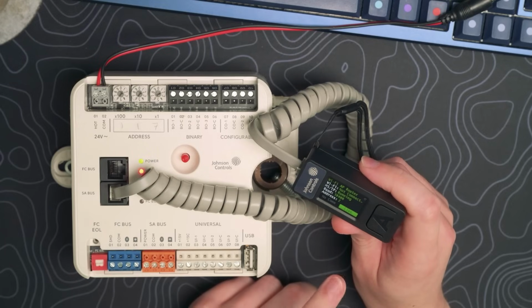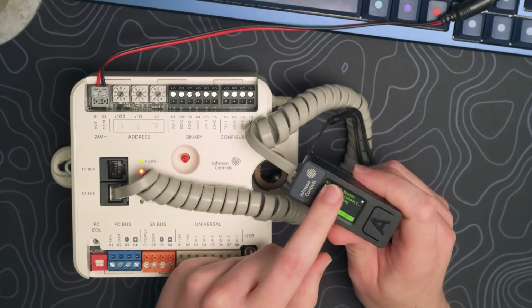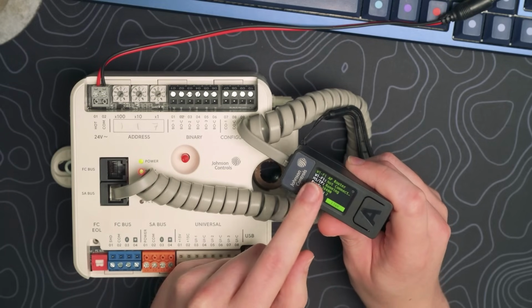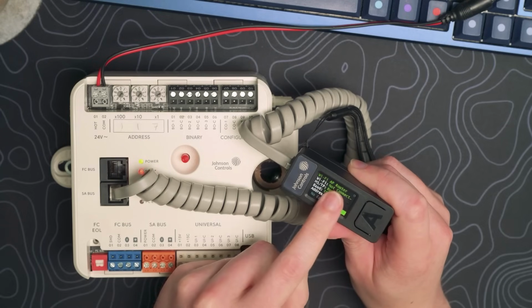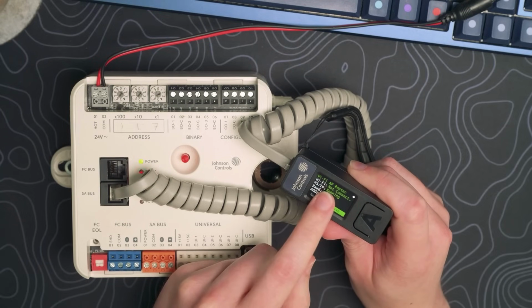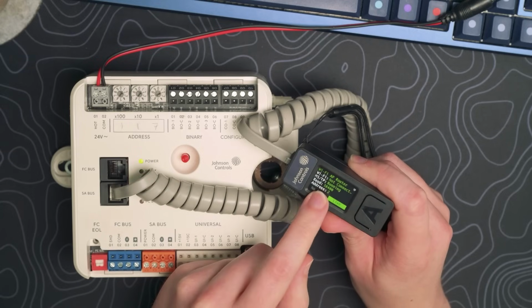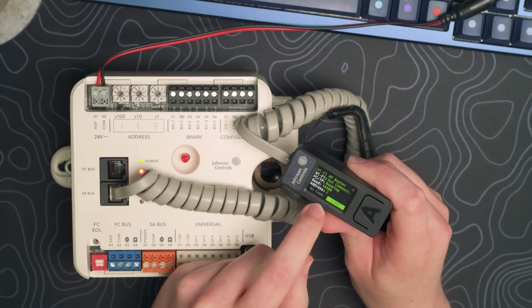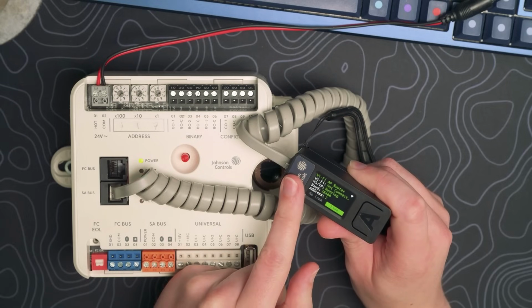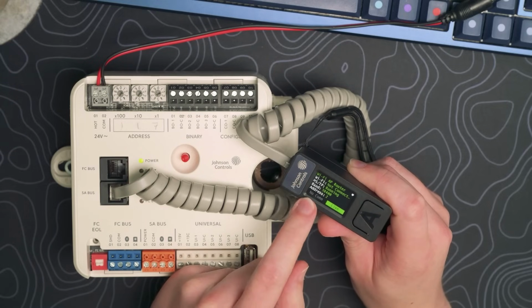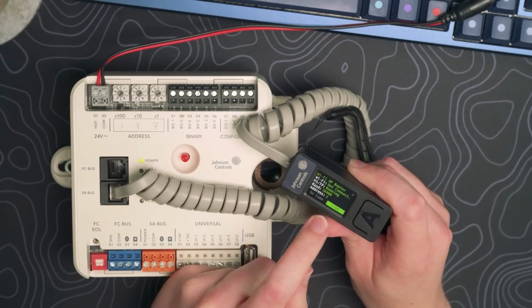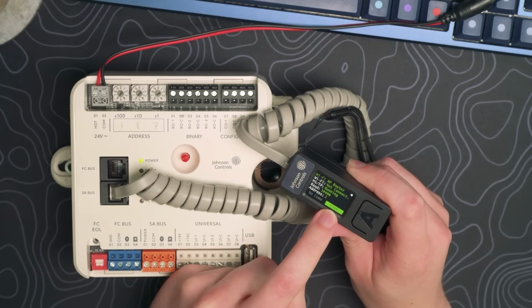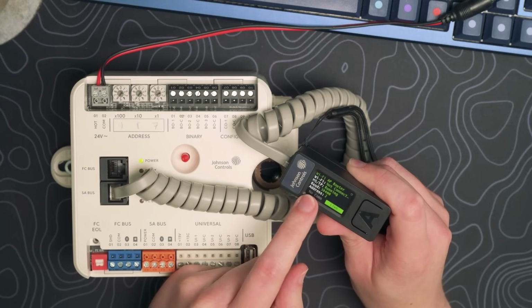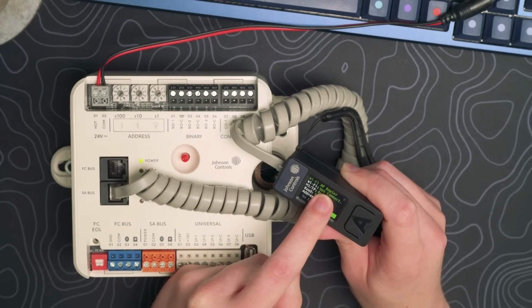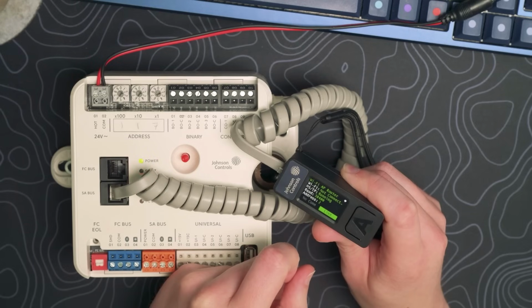So as you can see from the initial screen, we're in Wi-Fi access point router mode. No devices are connected to the Wi-Fi at the moment, but our MSTP is running. We're on 38.4 for our baud rate, and the address of the device itself is 2. Then we have a little status indication here. On the right, it says live, and that means that our BACnet MSTP is live and talking, and we have no connection. That's because we have no wireless devices connected.